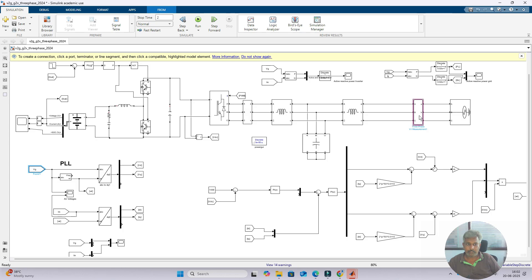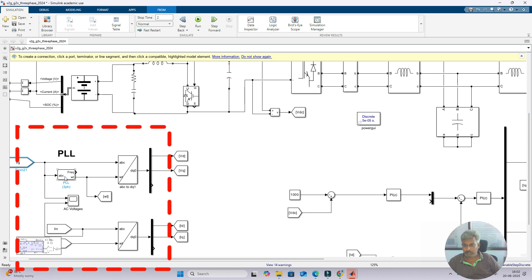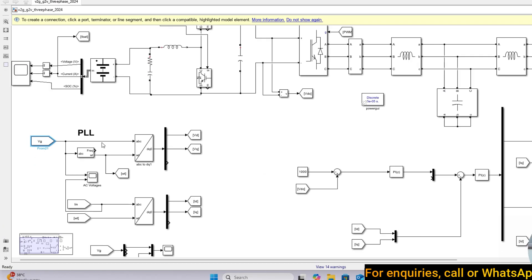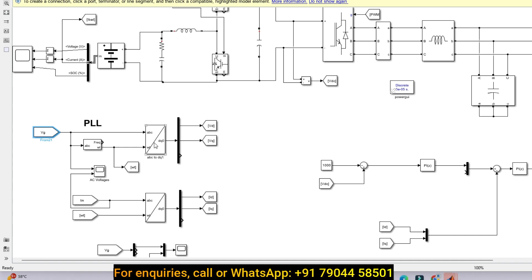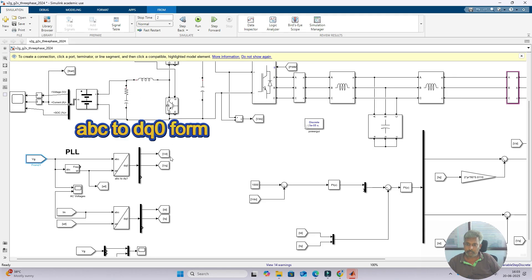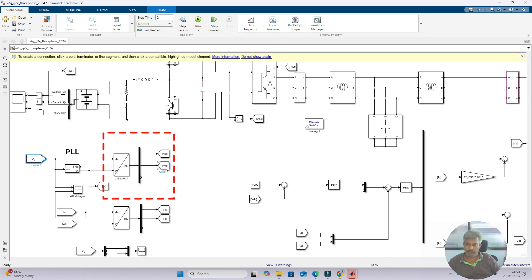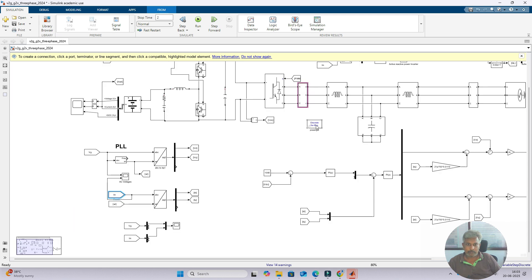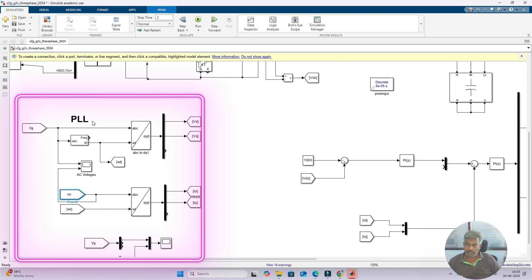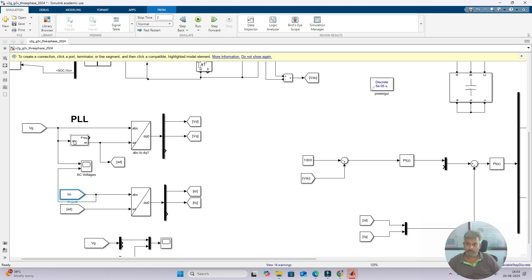Here we are measuring the grid voltage — the three-phase voltage at the point of common coupling. It is processed via a PLL which generates omega, which is the phase angle with respect to time. Next, the grid voltage VG is processed via ABC-to-DQ transformation because we are applying the DQ control concept in the feed-forward decoupling control. We convert ABC to DQ frame to get VD and VQ — the direct axis and quadrature axis voltages. The inverter current is also converted into DQ frame using Park transformation to obtain ID and IQ. PLL is used for synchronization of the converter with the grid.